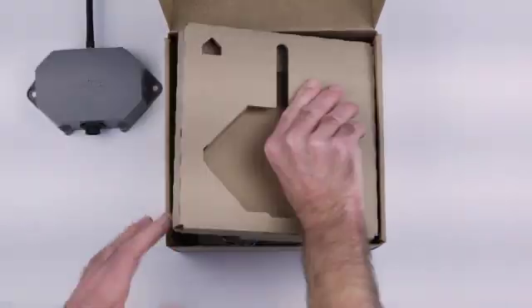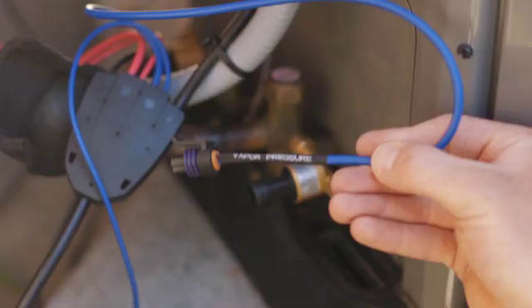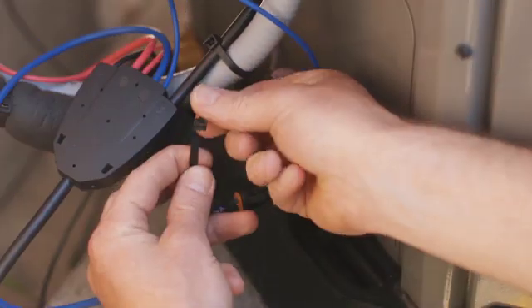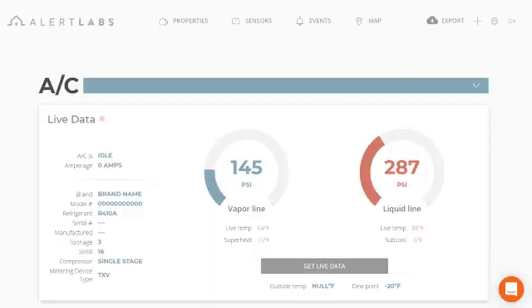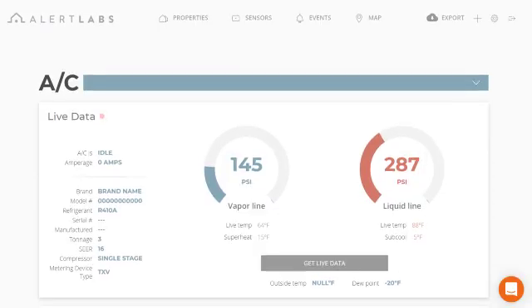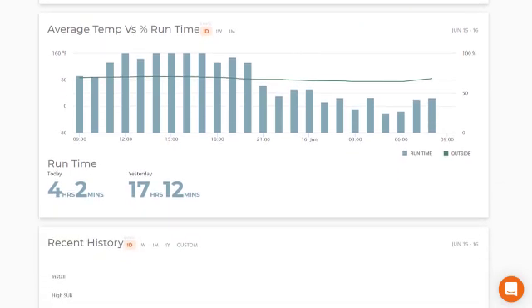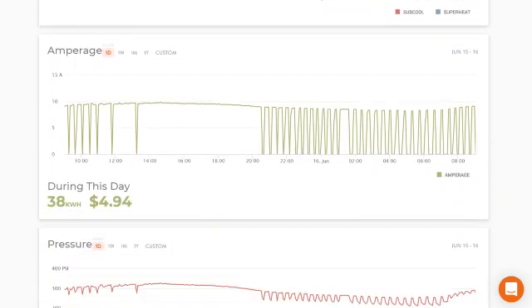So I told our tech — I went out there with them and showed him how to put it on. He picked it up right away. We monitored the system for about a week non-stop, and we ended up finding out that when the temperature would dip below 50 degrees, the indoor unit wouldn't come on, but the outdoor unit would just sit there and run and run and run. And the pressures would go crazy.